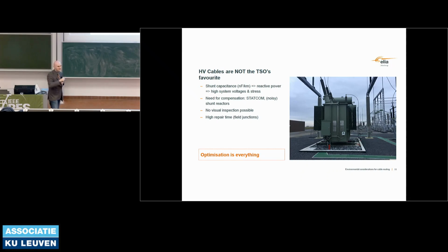You bury away the underground cable, perfect, but this reactive power from the shunt capacitance is really driving the voltage into the air. So in your substations, you need to put these kinds of devices, very noisy shunt reactors, just to draw out, to consume, let's say, it's not actually consuming, but technically seen, to really draw the reactive power out of the system to get your system voltages down again. So if people say, oh, we don't want to see the overhead lines, put cables underground, then you say, you get these machines for free. That's what you're choosing for.